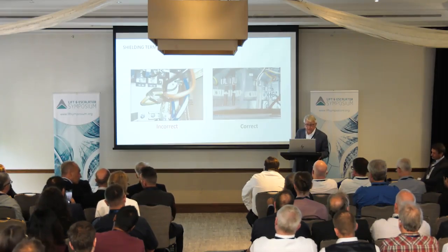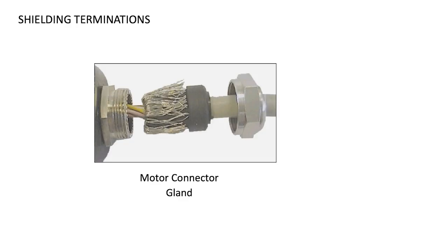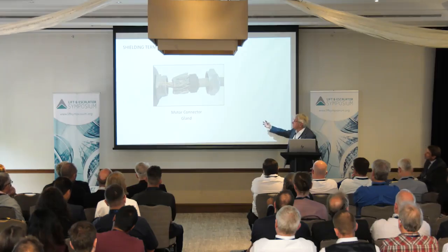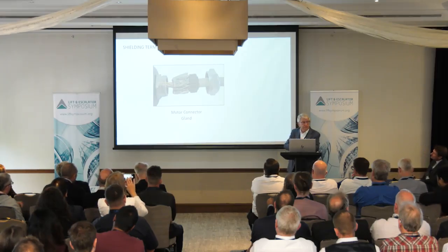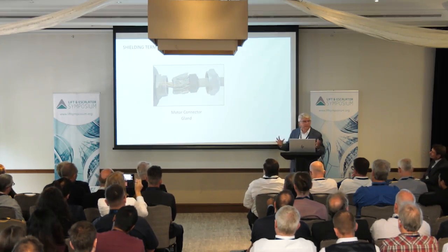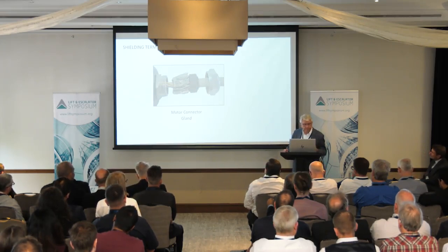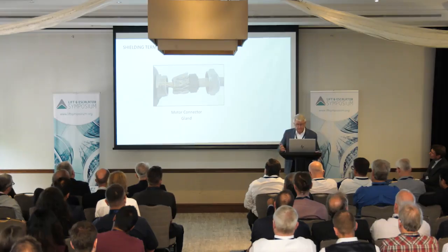And so here's another type of shielding that is very common on motor shields. It's a gland seal, a gland connection. And with these, you see, the shield is folded back. When you put these together, the entire shield is attached to, in effect, the motor, the body of the motor, and everything is grounded. So this is an effective system.